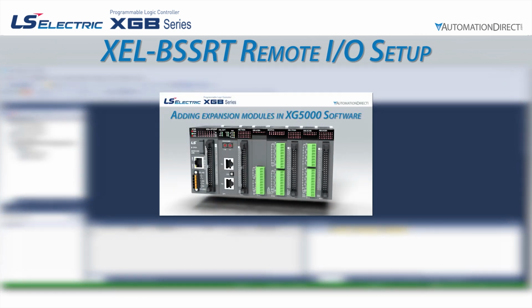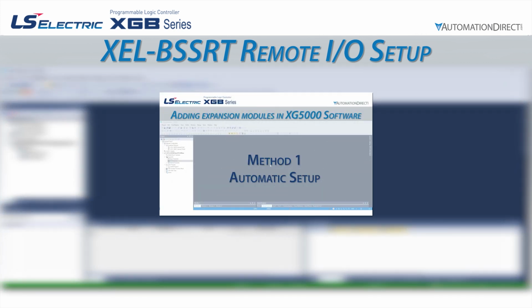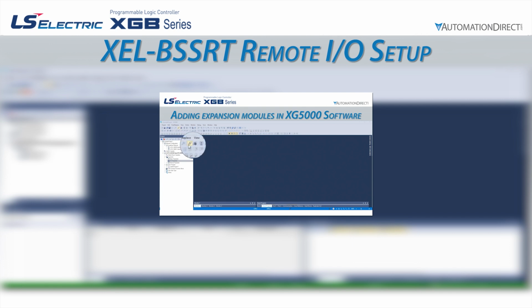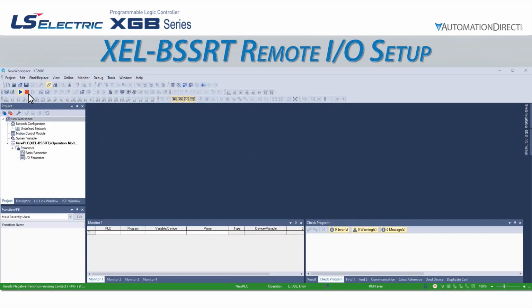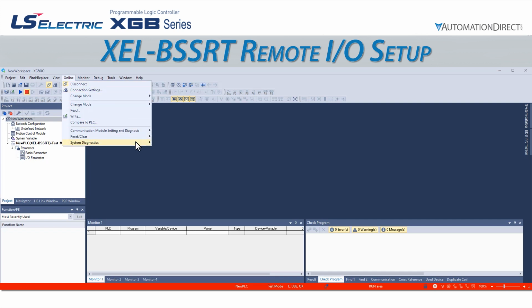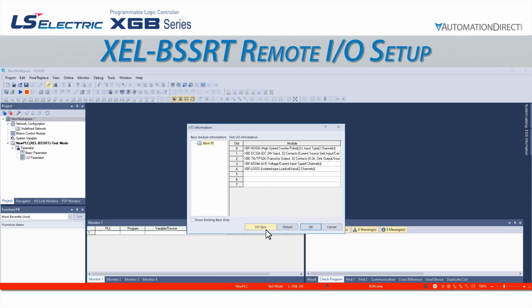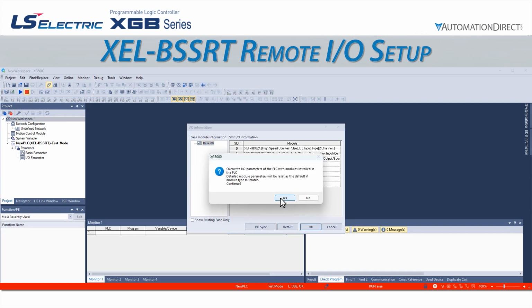We add I/O to the BSSRT exactly the same as the XEM CPU as well, so please refer to that video for further details. If we aren't in test mode, we will need to enter it now, and we will use the I/O sync function by going to Online, System Diagnostics, I/O Information. This opens the I/O Information pop-up window, and we can select I/O Sync. It will give us a warning saying that we are overwriting the existing module information, and this can cause information to be erased. Since we are bringing the empty project into sync with our actual hardware, we are okay with this, and we'll select Yes.